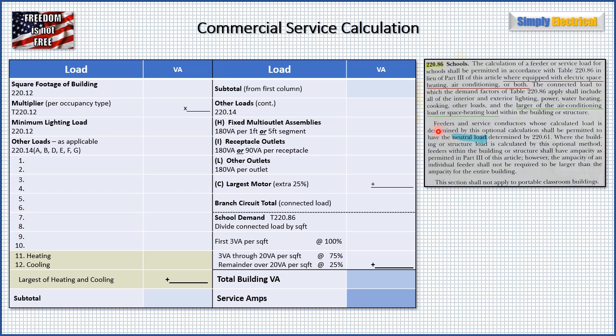Before we move on — feeders and service conductors whose calculated load is determined by this optional calculation shall be permitted to have the neutral load determined by 220.61. Most calculations allow you to use 220.61 to size your neutral load. It also says where the building load is calculated by this optional method, feeders within the building shall have ampacity as permitted in Part 3 of this article; however, an individual feeder shall not be required to be larger than the ampacity for the entire building. So any feeders inside the building can be calculated by Part 3 — this optional method is in lieu of Part 3 for the service only. Last thing: this section shall not apply to portable classroom buildings.